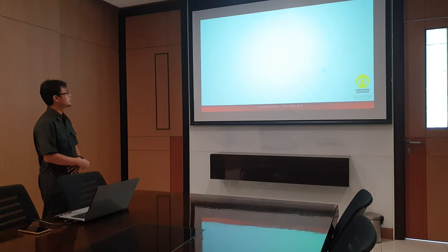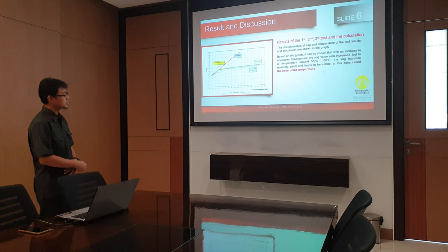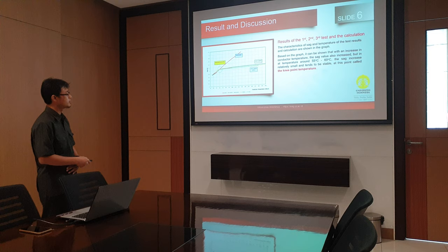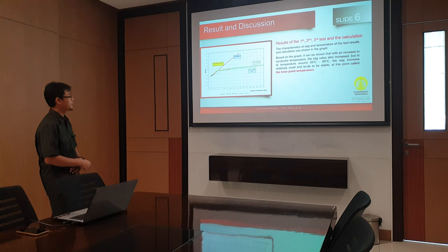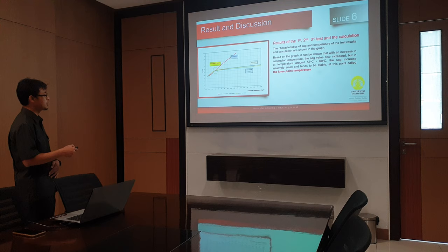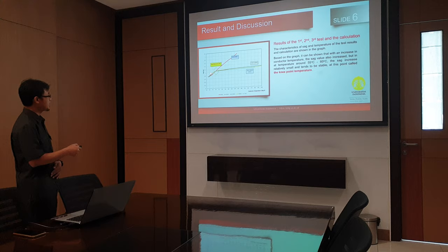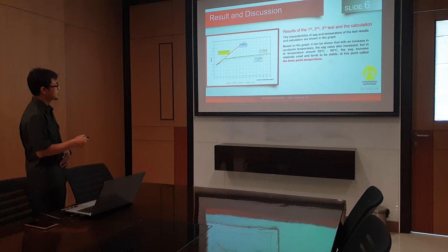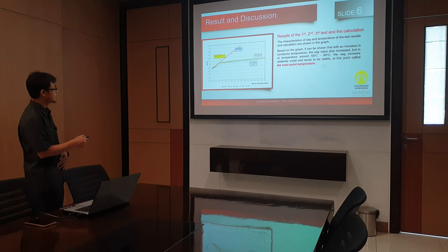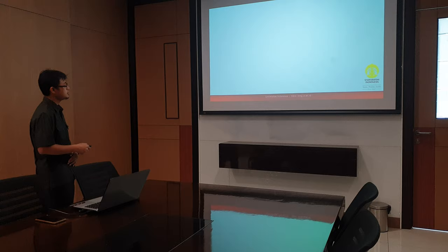From the graph, we will actually know the Knee Point Temperature. Result and discussion. The result of the first, second, and third test and the calculation show the characteristics of the sag and the temperature. Based on the graph, it can be shown that as the conductor temperature increases, the sag value has increased. But in the temperature range around 50–60 degrees Celsius, the sag increase is relatively small, and the trend has changed. This point is known as the Knee Point Temperature.